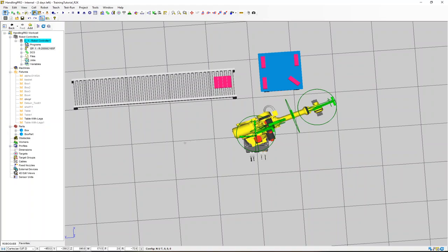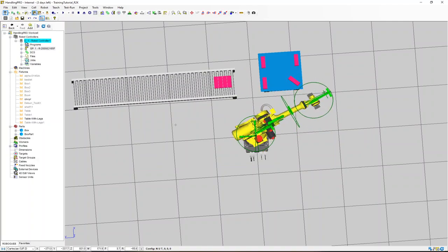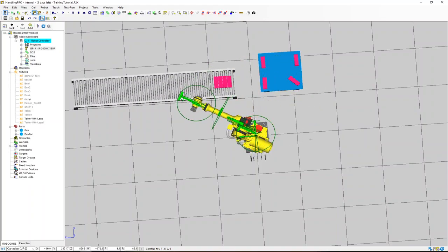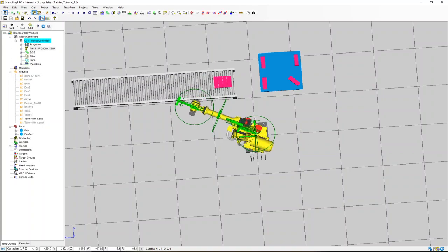The way we do that is we set up a light curtain on the left and a light curtain on the right. When the left light curtain gets broken, it tells the robot, disable your CPC, go over here and only work here and ignore anything going on there. And then when I'm over here working, I can use that same safety signal to disable this zone, let someone come in and out. So basically you're giving the robot the ability to not stop when a light curtain is broken because DCS is going to confine it to working on the side where the human is not there.